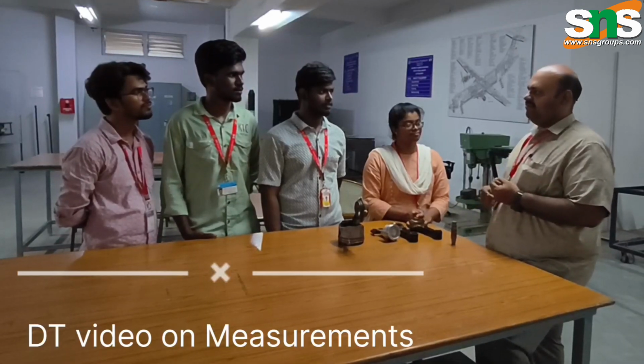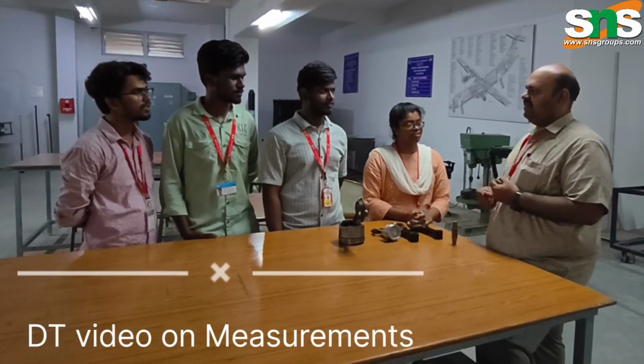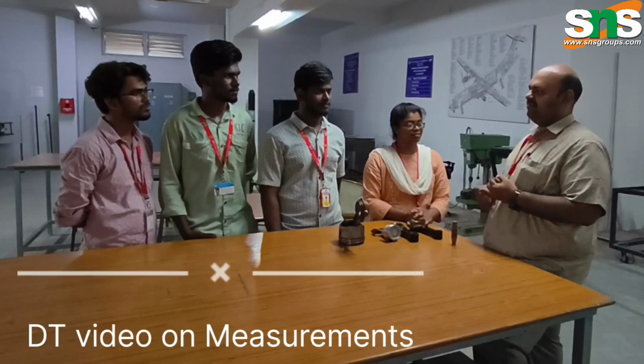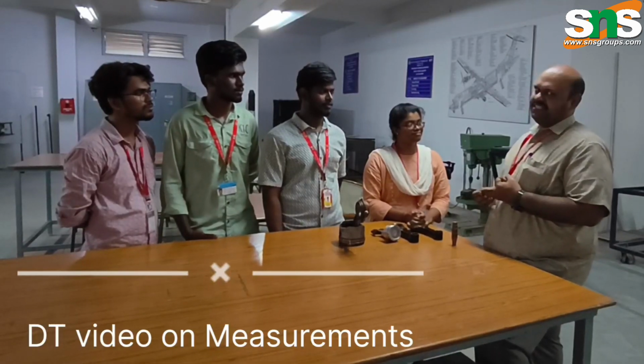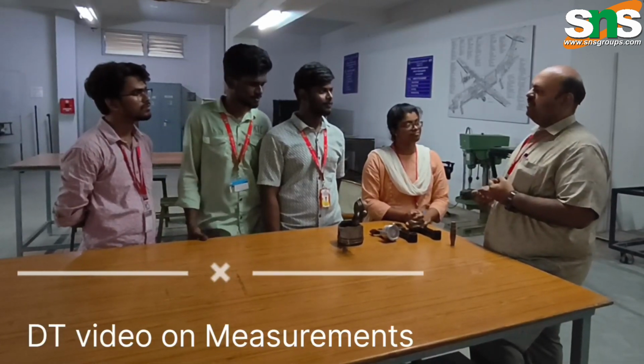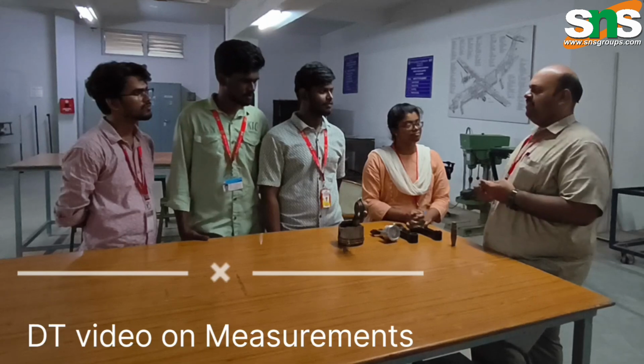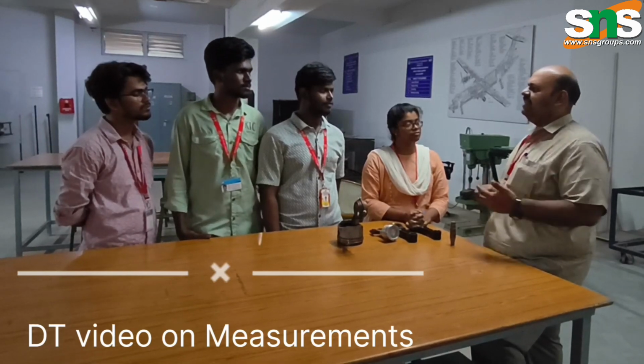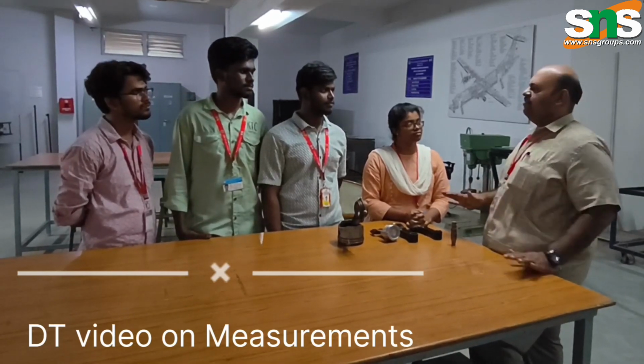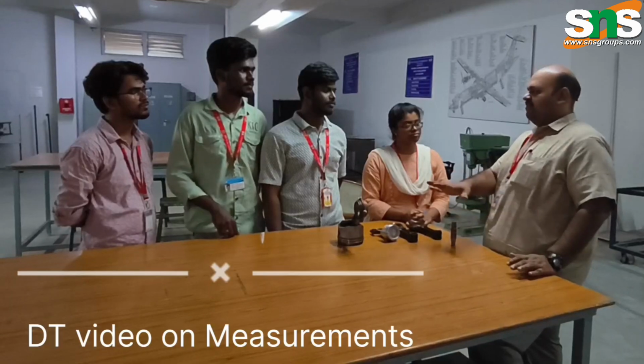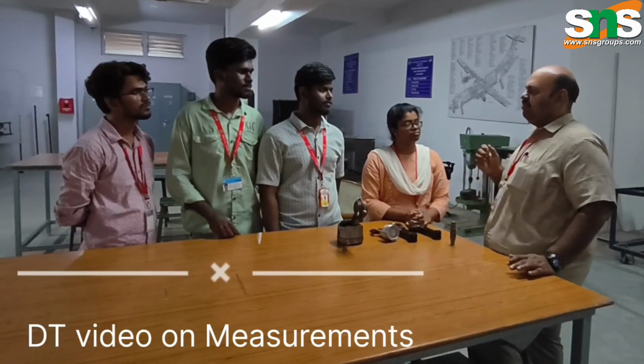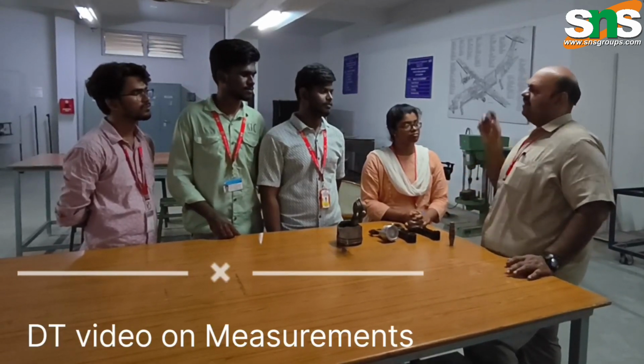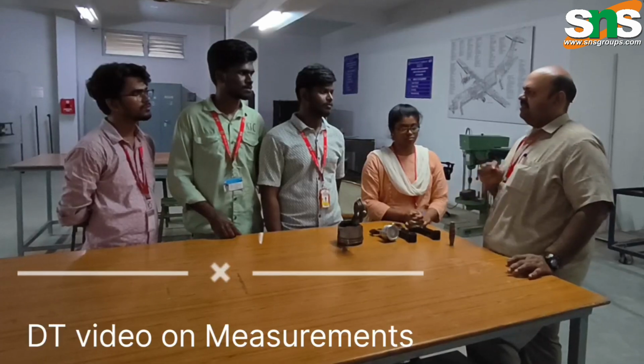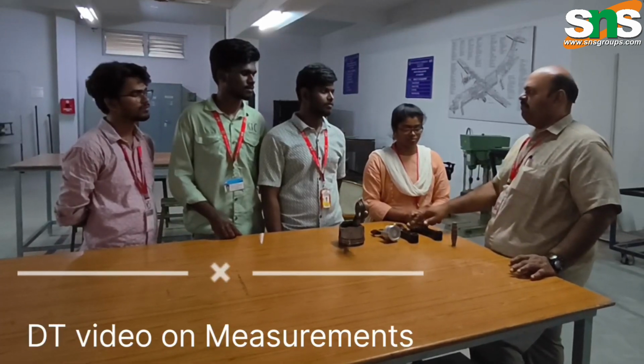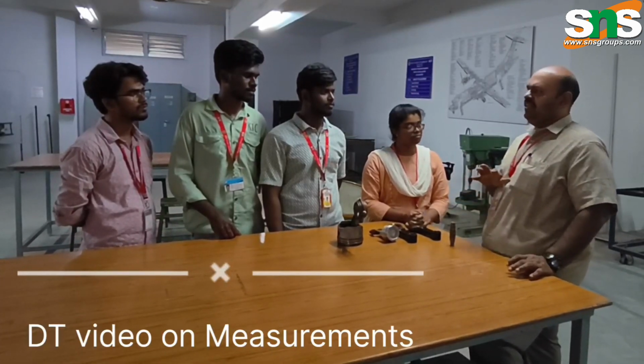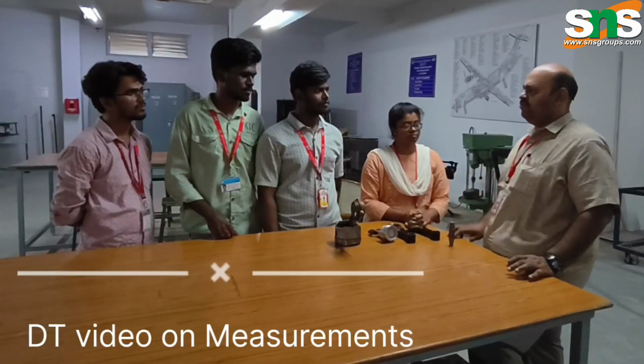Vernier caliper, inside micrometer, then bore gauge. Okay. So bore gauge, bore dial, telescopic gauge, we have different instruments, and finally CMM. We cannot touch the component, we can keep it on a surface plate, and then we have a probe just to touch the points and then find the diameter of the ring. Okay. So these are the many ways we have measuring instruments.